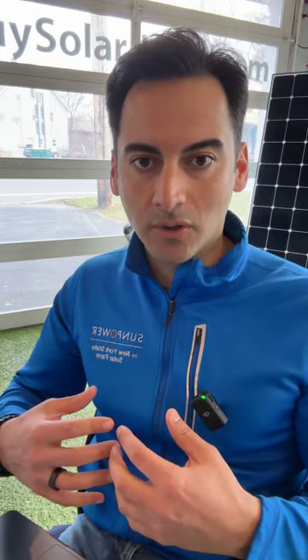The guidance I've gotten is that this new grid profile, unlike ones in the past — when the grid goes down or has a drop in voltage or hertz on the lines — instead of the inverter shutting off immediately, what it's going to do is ramp down. And after five minutes, if the grid doesn't come back, it's going to shut the inverter down.